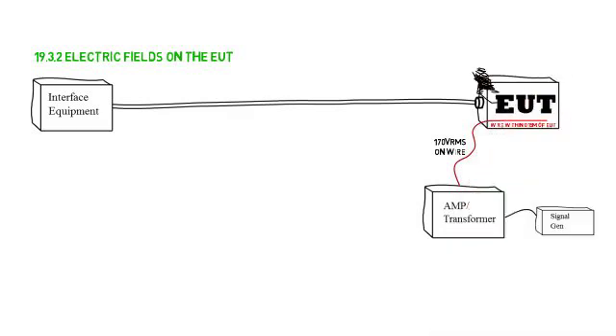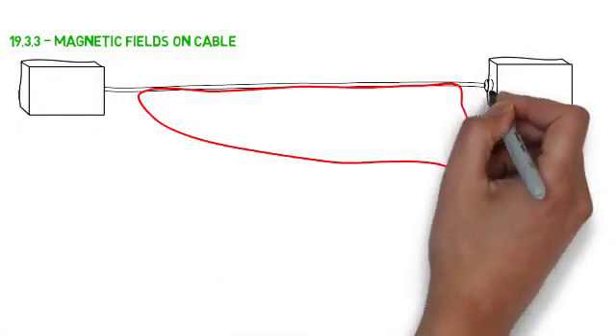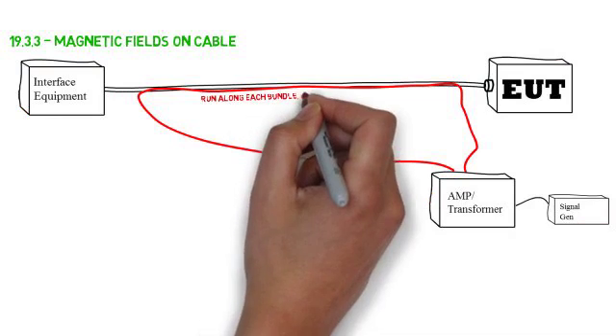For magnetic fields on the cable, run a high current wire along each bundle of the EUT to be tested. This wire should be within 5 millimeters of the bundle. Apply the forward current specified per your category.